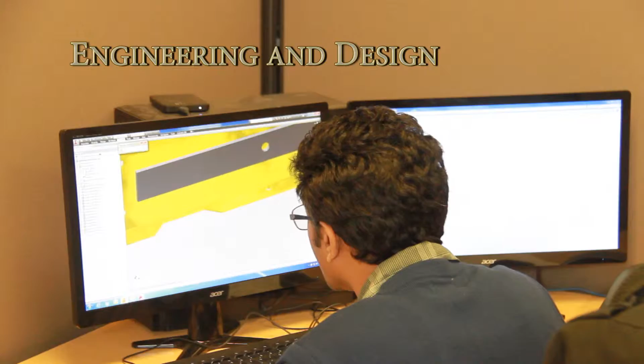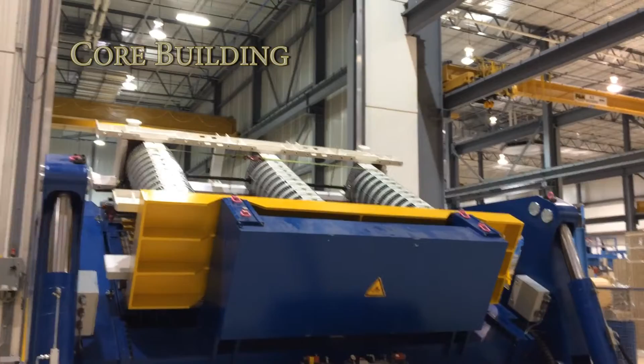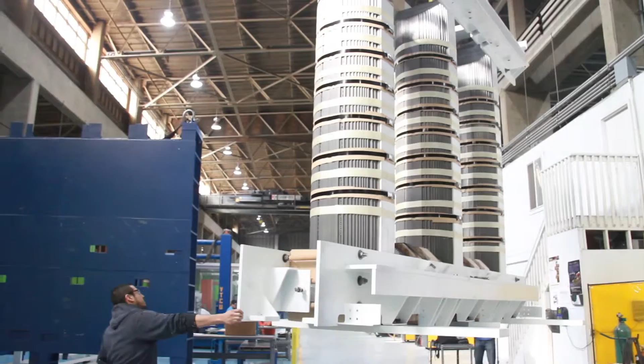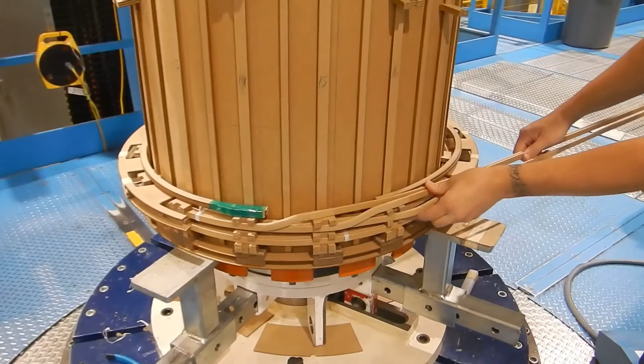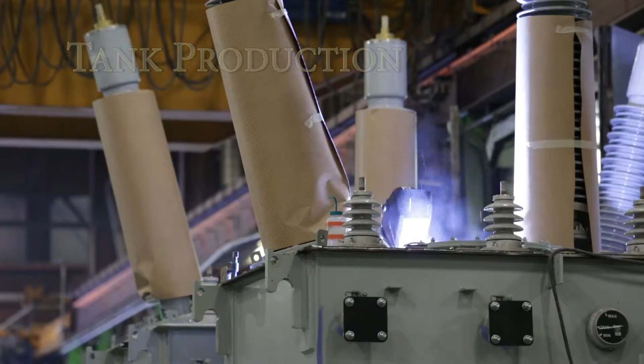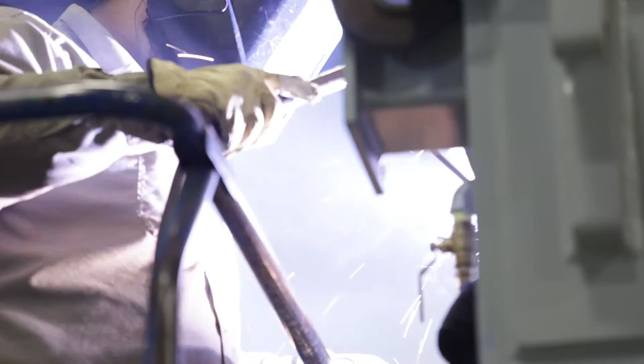LPT design is complex, balancing the cost of raw materials, electrical losses, manufacturing labor hours, plant capability constraints, and shipping constraints. The core is the most critical component of an LPT, requiring a highly skilled workforce and cold-rolled, grain-oriented laminated electrical steel. Windings are predominantly copper and an insulating material. Excess moisture must be removed from the core and windings because moisture can degrade the dielectric strength of the insulation. A tank must be completed before the windings and core assembly finish the drying phase, so the core and windings do not start to reabsorb moisture.